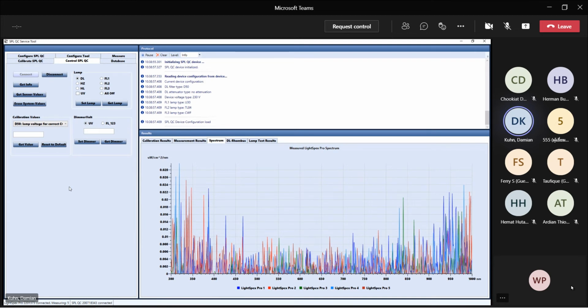So if you're actually selecting that and click on get value, you're going to see the lamp voltage that is currently configured on that connected instrument, and that's what's applied when somebody presses the D65 or the D50 button on that instrument, or that's what's used at the beginning of the calibration sequence for daylight. Now, of course, it can be that this is way higher, and it's on 108 here because I already demonstrated during a previous training how to reset it to default. So basically really select the light source and the lamp voltage for correct CCT.